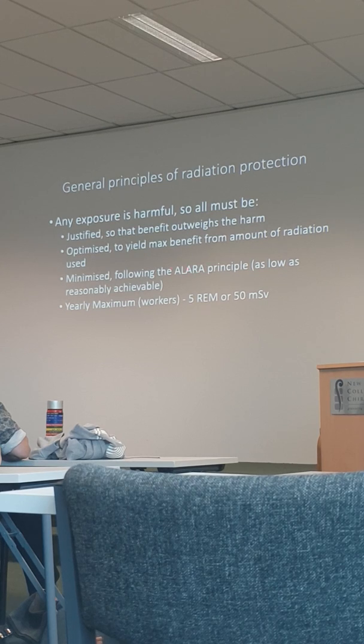Minimize, obviously need to follow ALARA, as low as reasonably achievable. And then you also need to follow the laws in the country to look at the maximum for workers, for the general public, pregnant patients, all that sort of thing. So the yearly maximum for workers is 5 rems, or 50 millisieverts.